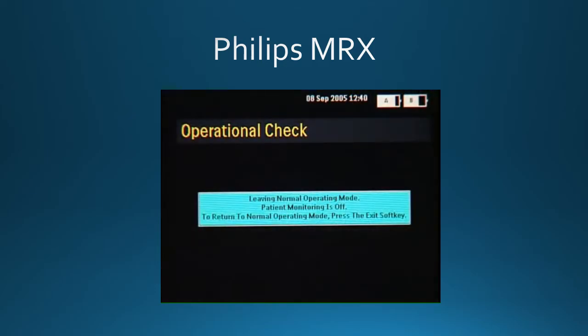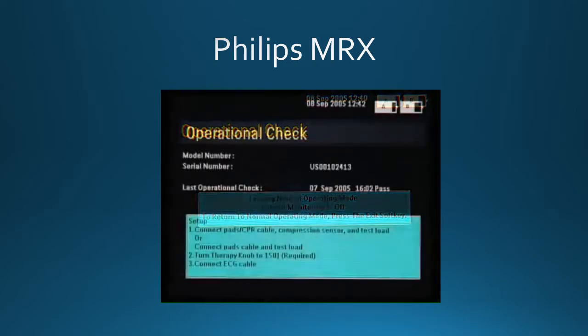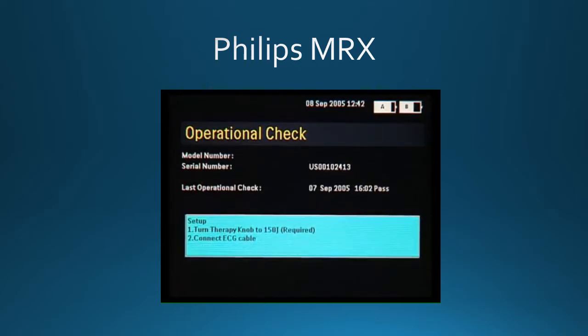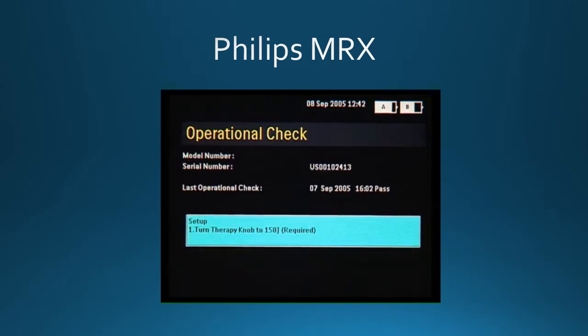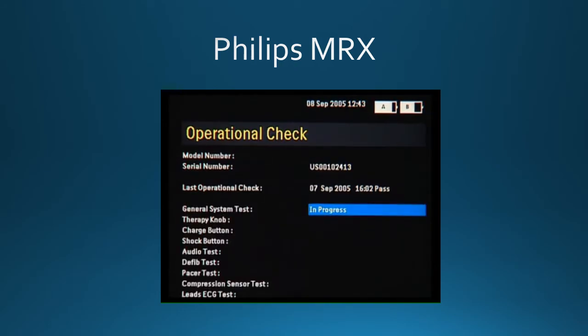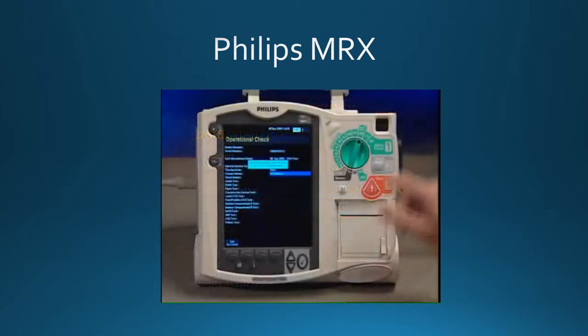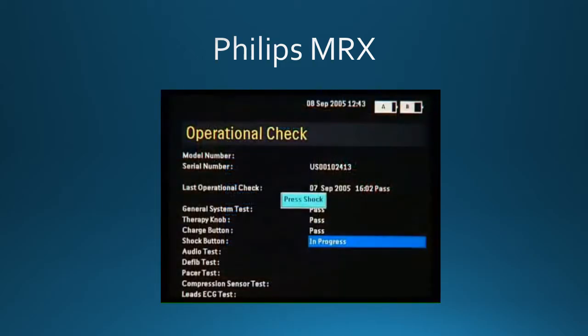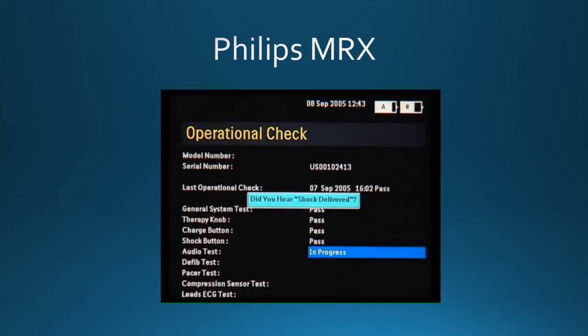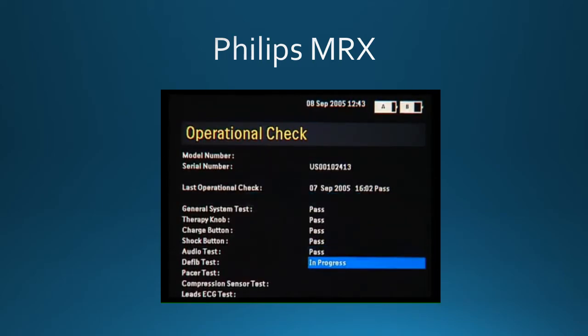This message lets you know that you are exiting from all clinical functionality and entering a test mode. Be sure to connect all cables and accessories as instructed on the display prior to running the operational check. If everything is set up as expected, the series of tests will begin. If not, you will be prompted to correct the setup, proceed with the test based on the current setup, or exit op check. As each test is run, the message window In Progress displays. When prompted, follow the on-screen instructions. You are given a pass or fail indication upon completion of each test.